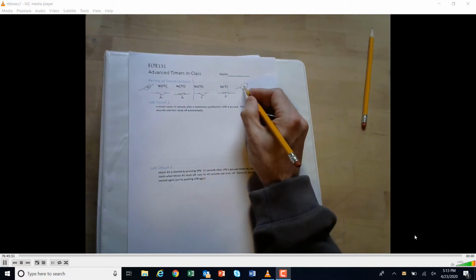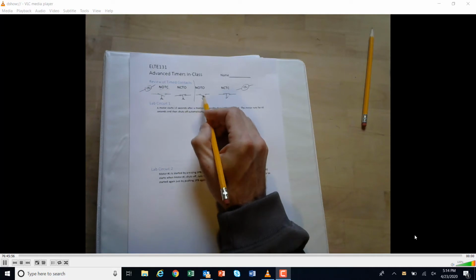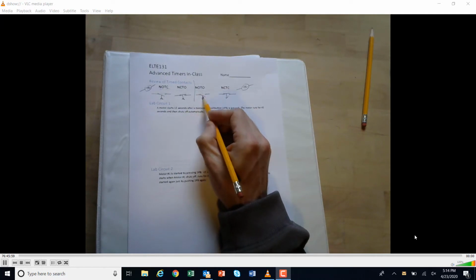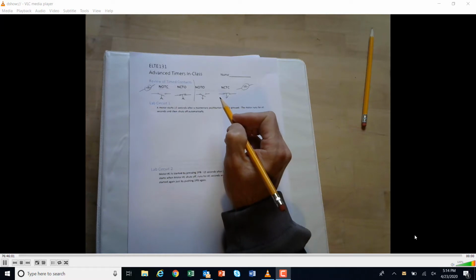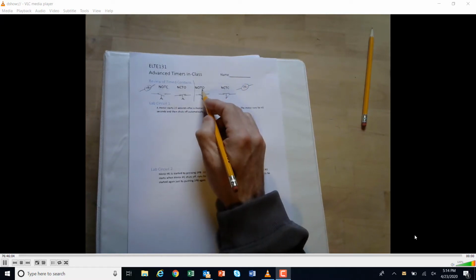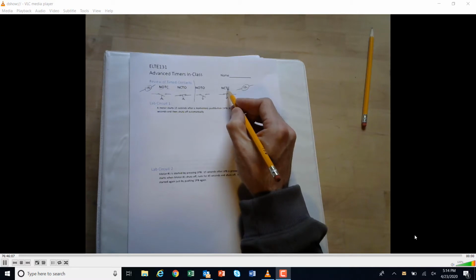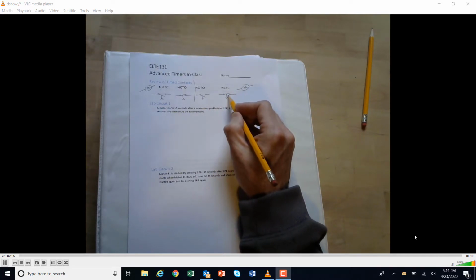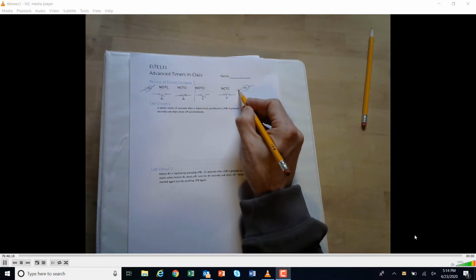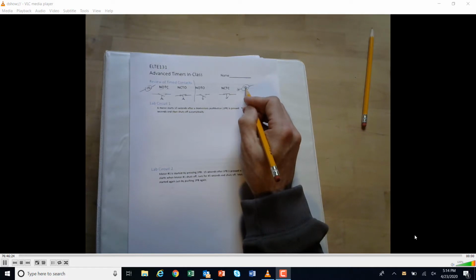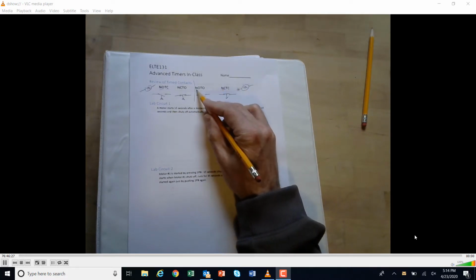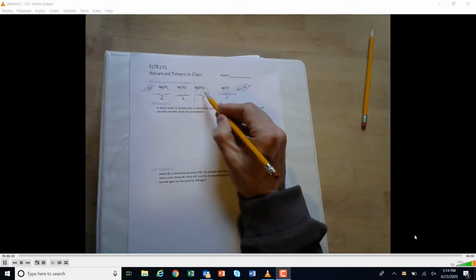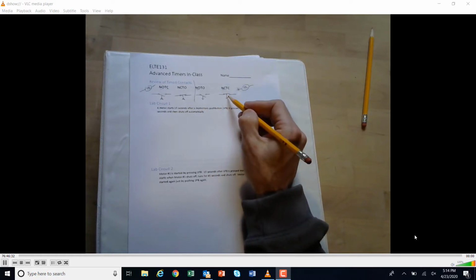Now, these are the off delay. When you energize the coil, this one's open, so it closes so that we can eventually open it again, because that's what it says. And this one is closed, so it's going to open. So when we energize the coil, they change their states, but they don't start timing yet. We have to remove voltage to the coil, and that's when the off delay starts timing, and then they return to their normal conditions: this was normally open and it times back to open, and this was normally closed and it times back to closed.